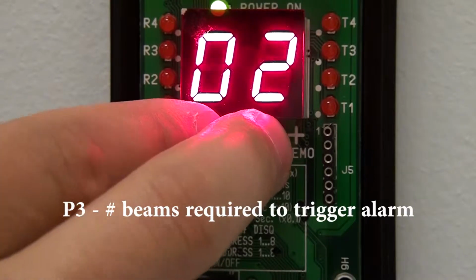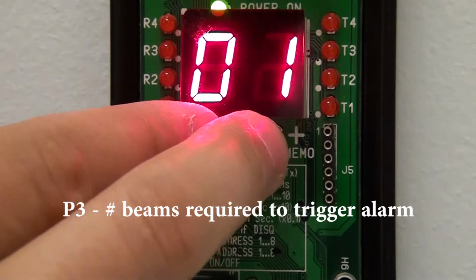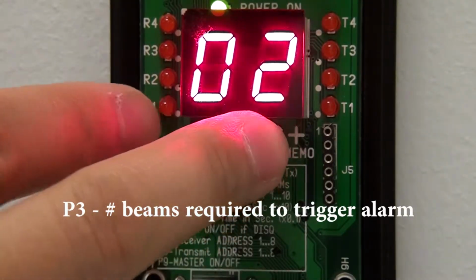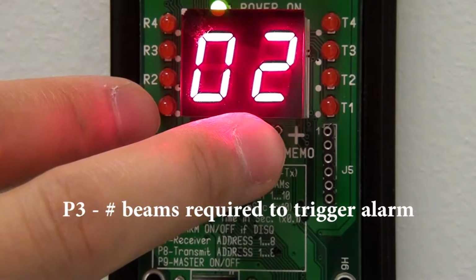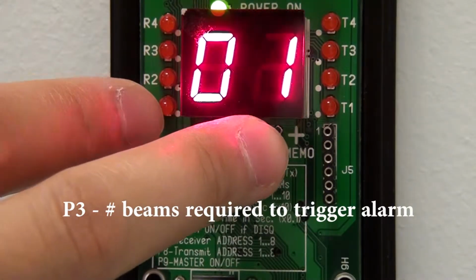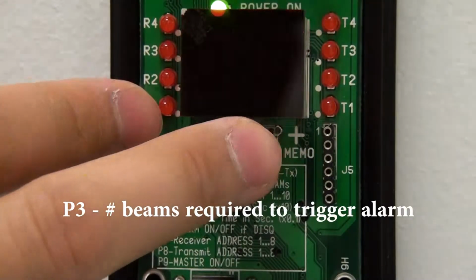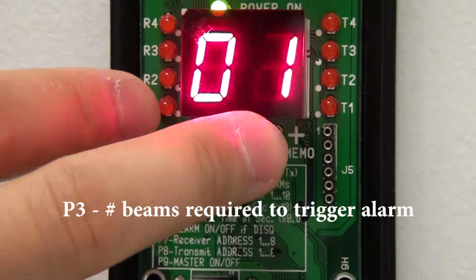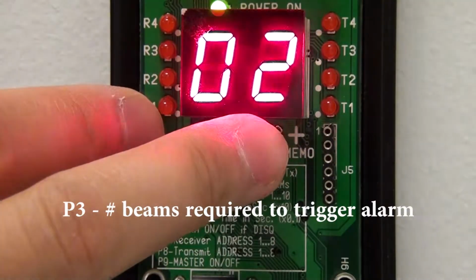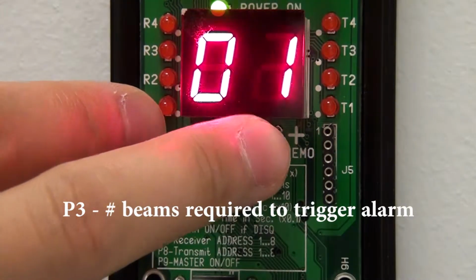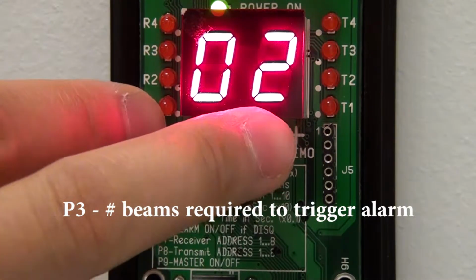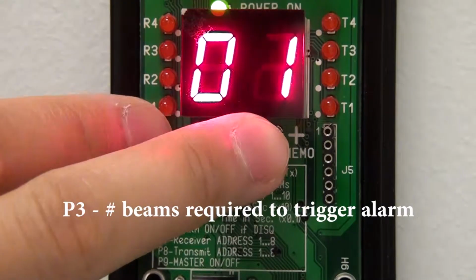P3 is the amount of barriers required to break the beam. So here we can only choose 1 and 2 because we only have 2 beams available. If you choose 1, only 1 beam is required before the alarm trips. Or if we choose 2, then we'll have to break both barriers at the same time before the alarm trips.